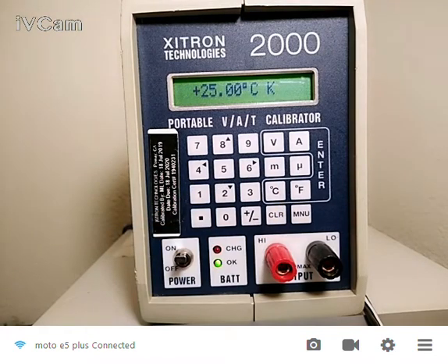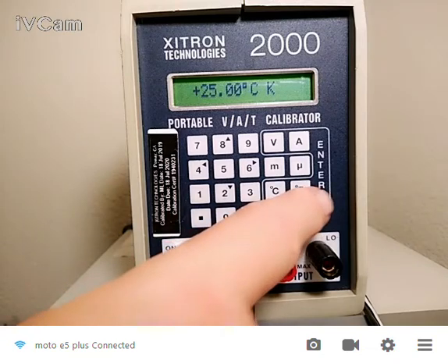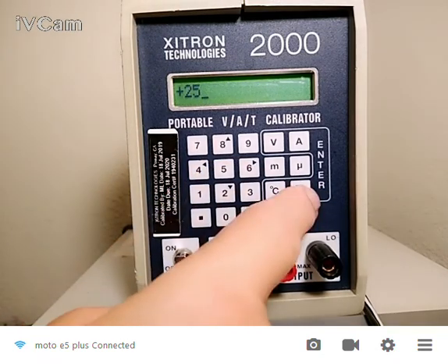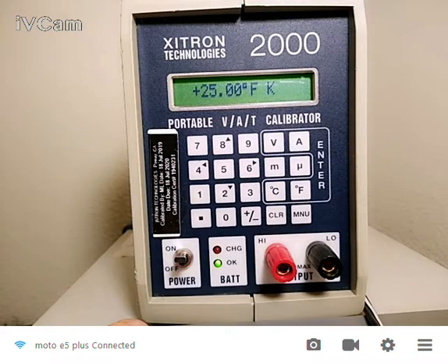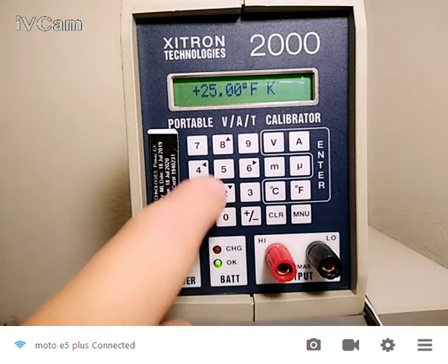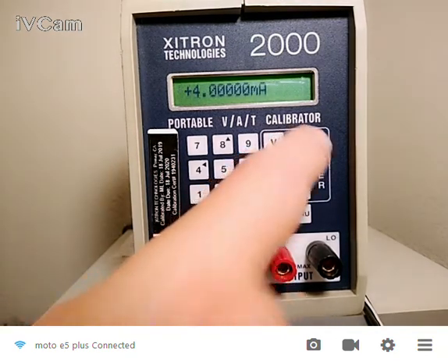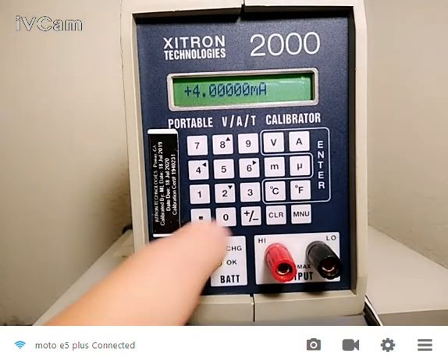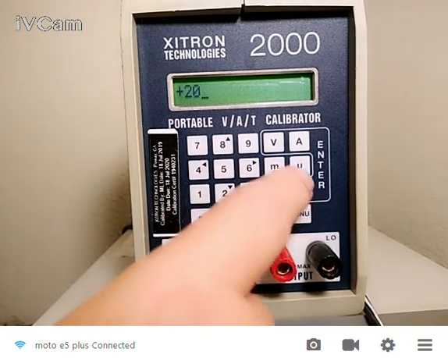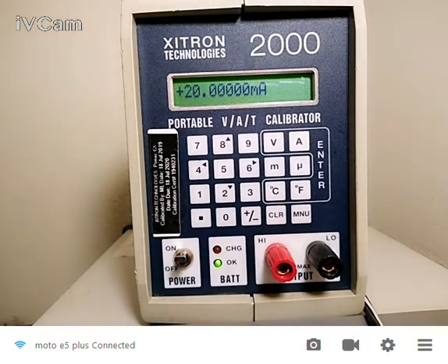And you notice that we have 1/100th of a degree C resolution, so very, very high resolution. The DC accuracy on this is 10 parts per million, which is about 10 times better than other calibrators in this price range. So it's a very, very precise instrument. If I want F, I can say 25F. If I'm calibrating 4 to 20 milliamp current loops, I can just say 4 milliamps, and then it outputs in current. I can put 20 milliamps, and output in 20 milliamps.